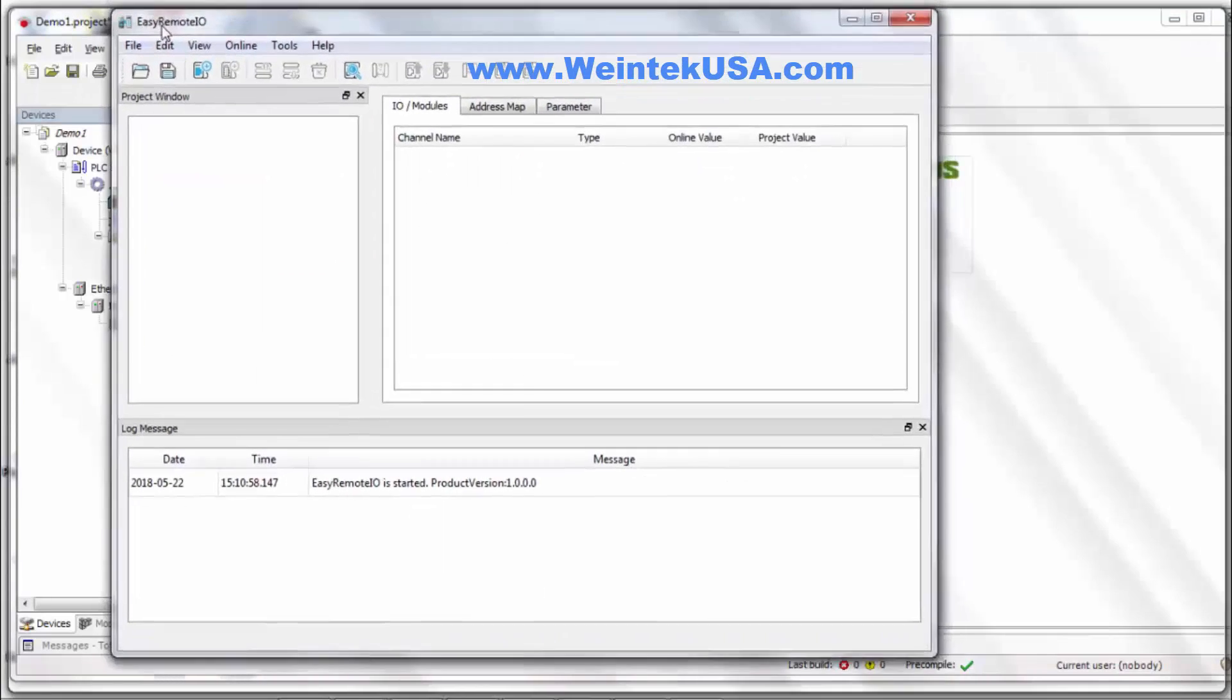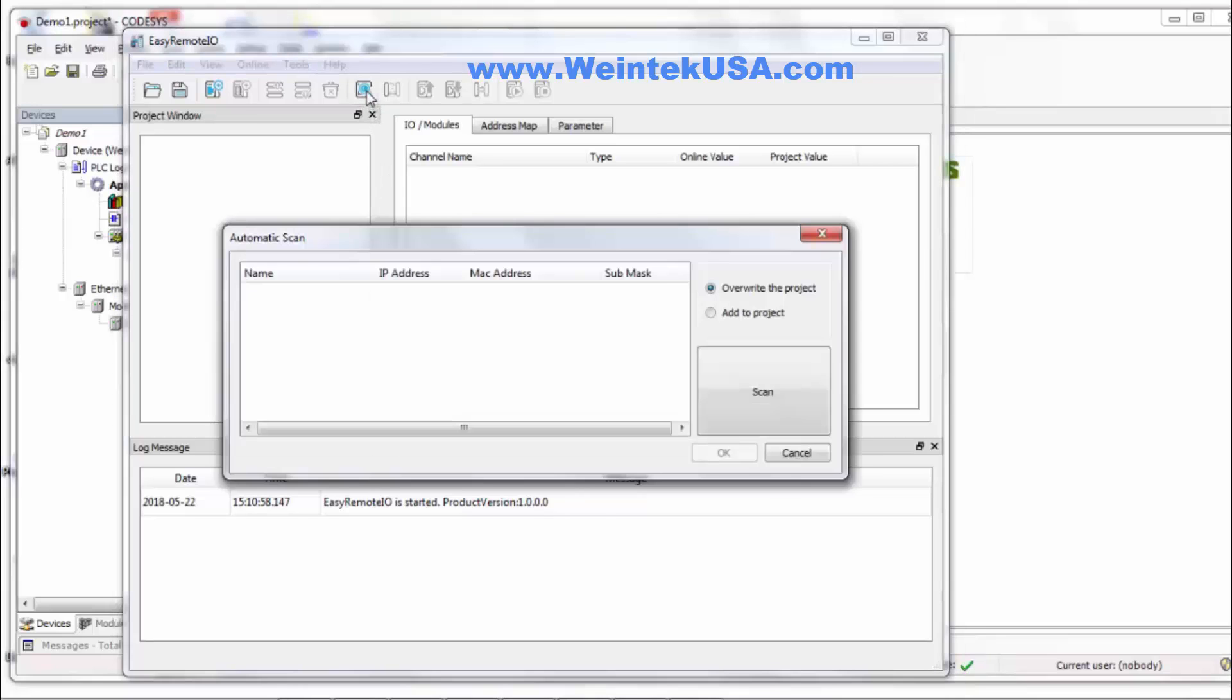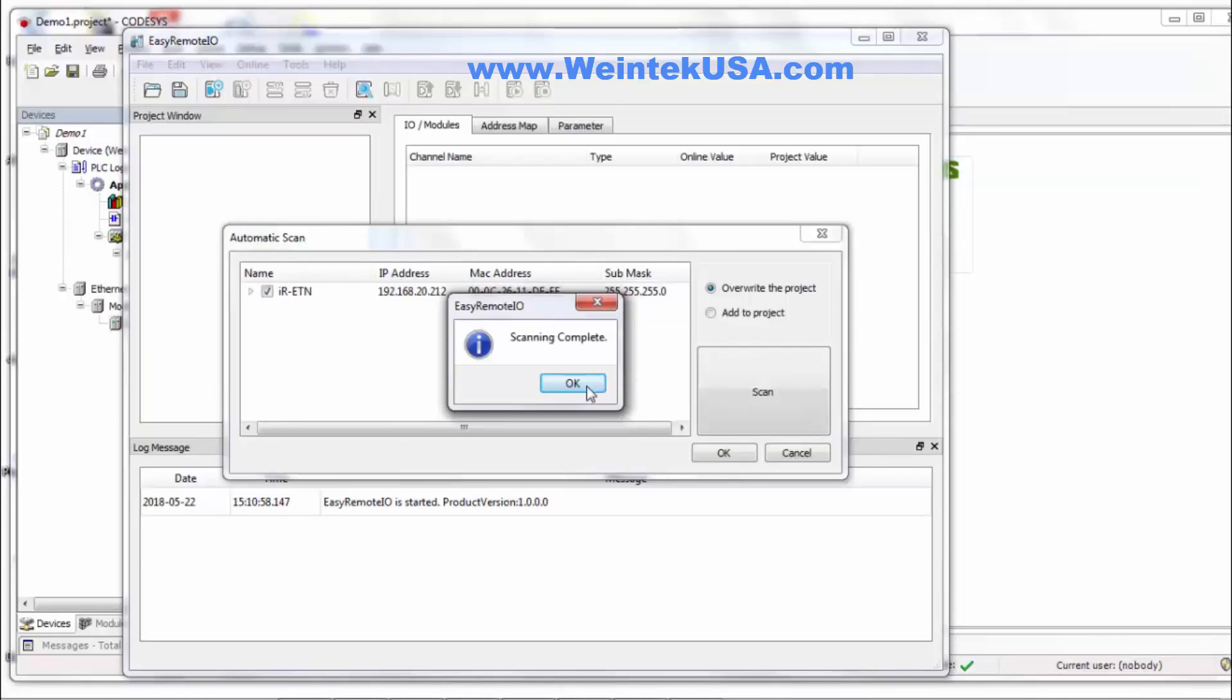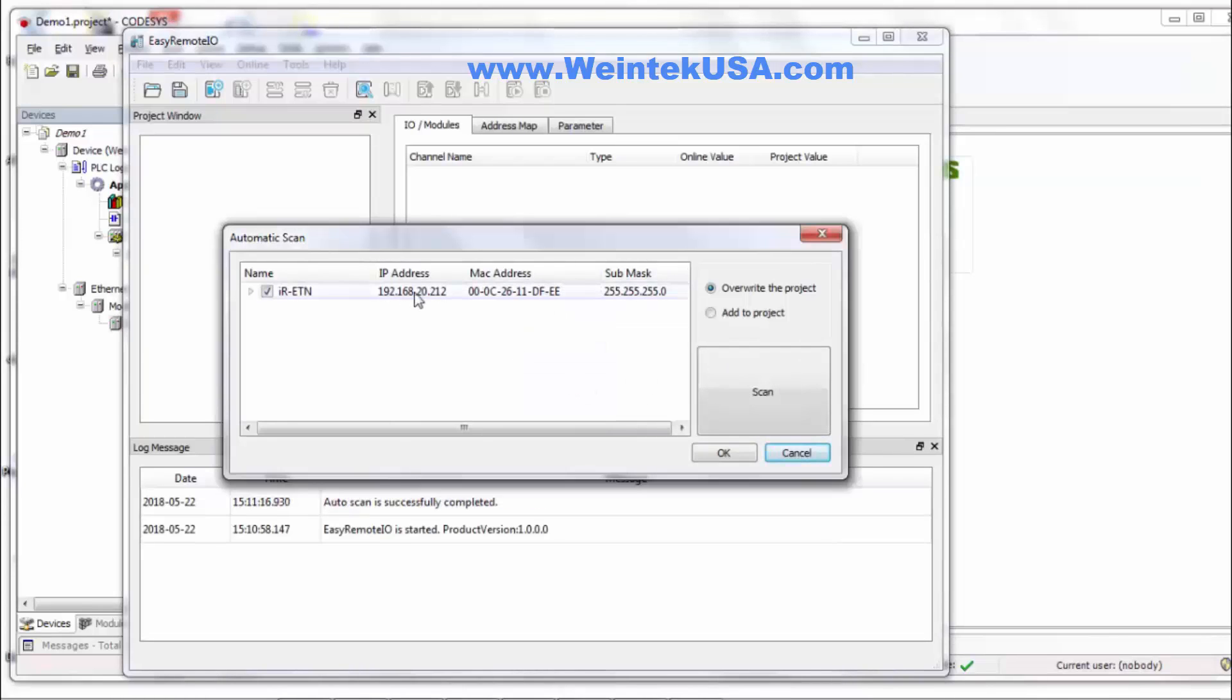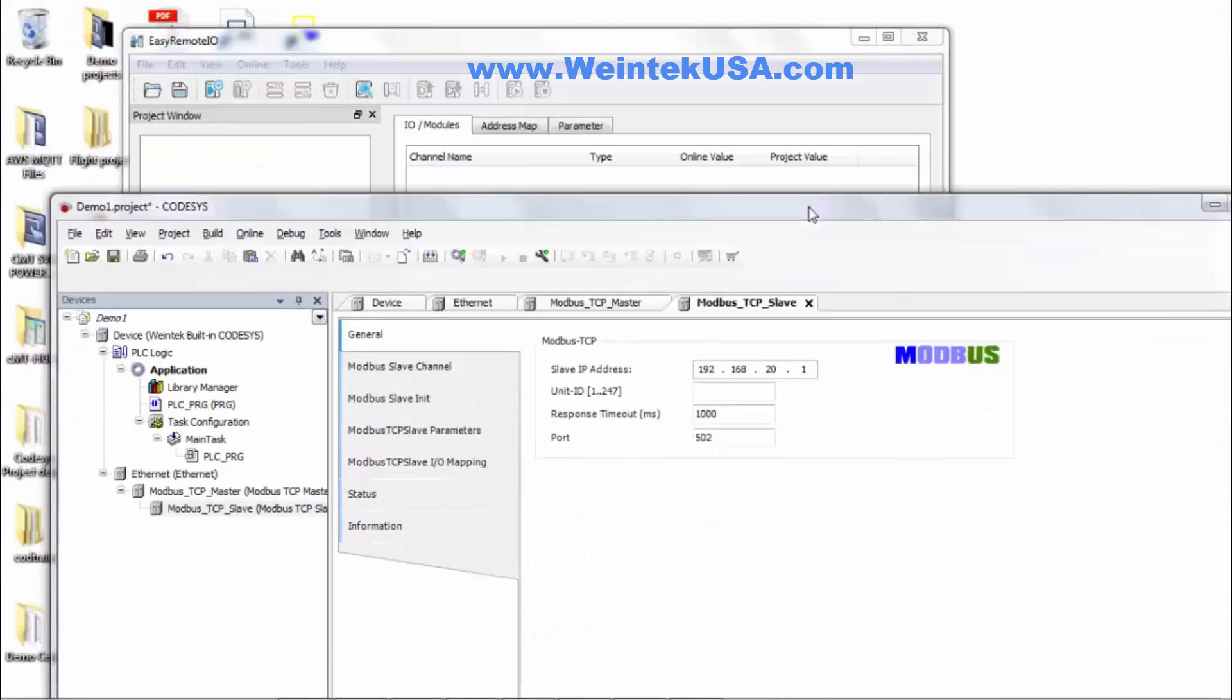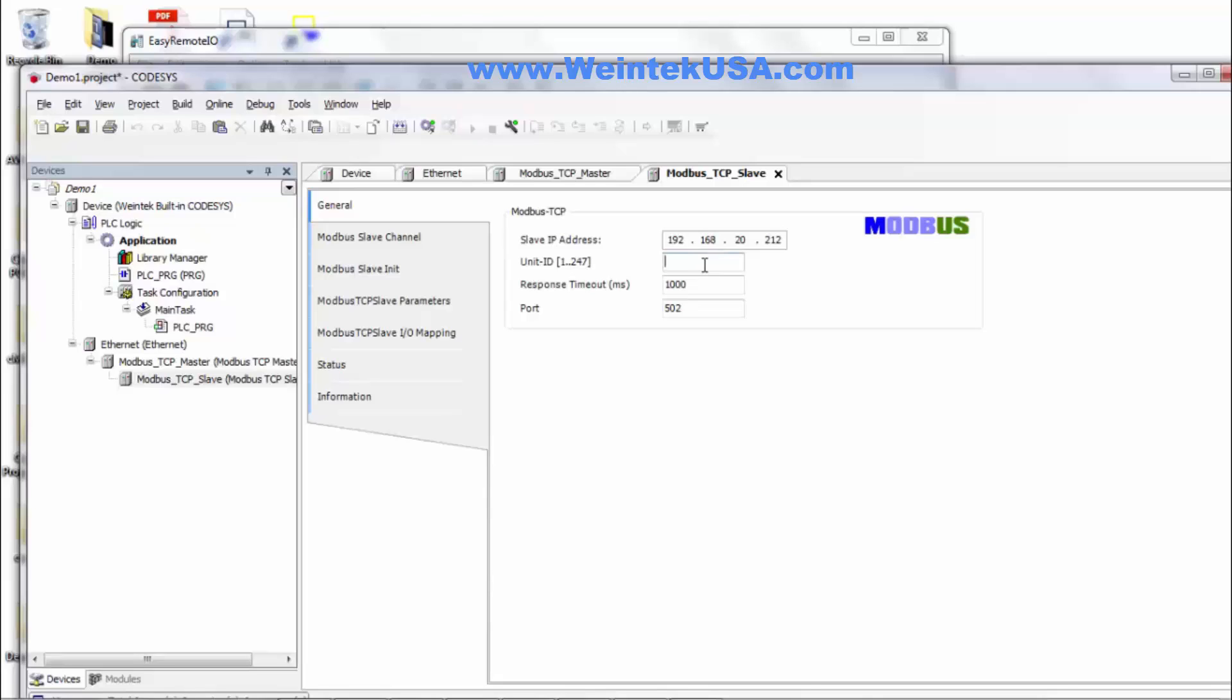Now if you've already got it all connected you can use the Easy Remote I.O. tool here and scan your network. And it shows us our IP address on it. So that's what I want to enter in here. And this is unit 1, port 502. All that stays the same.